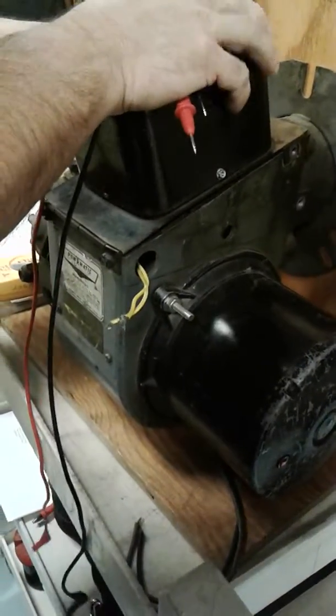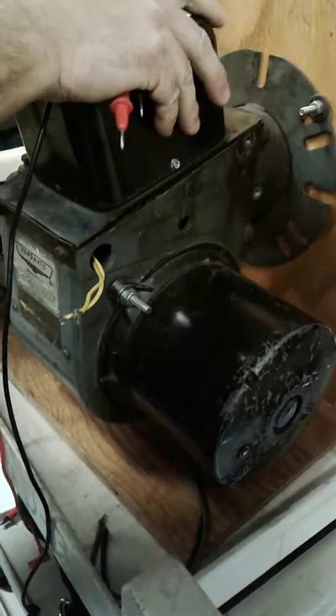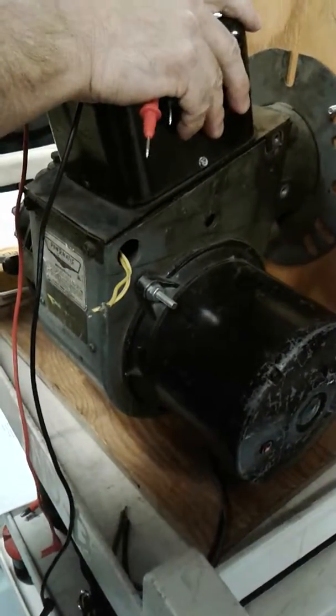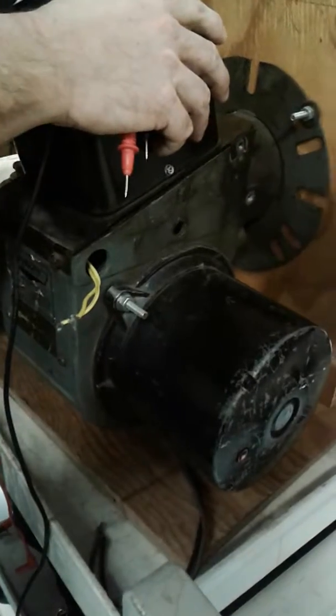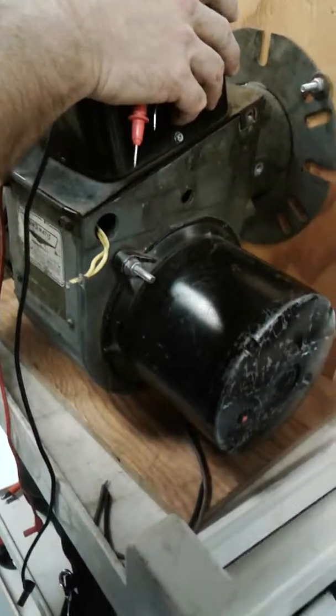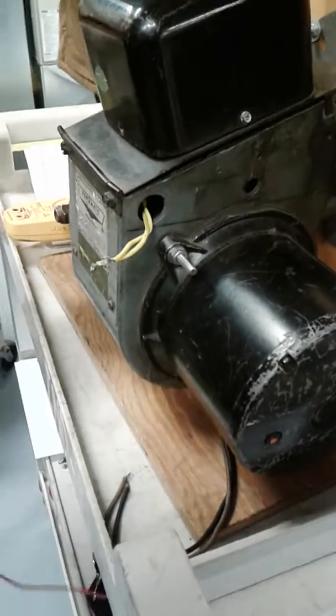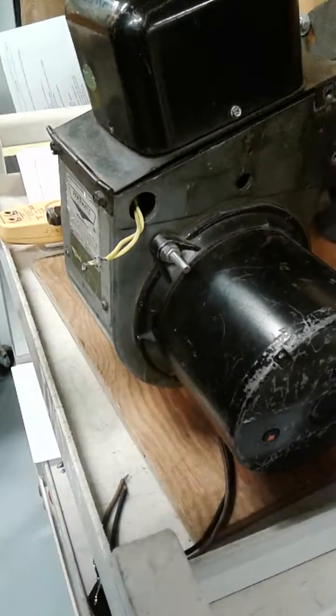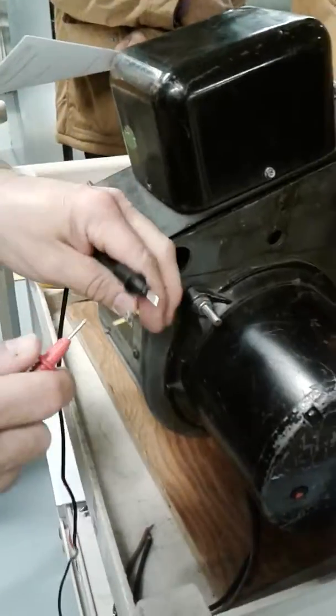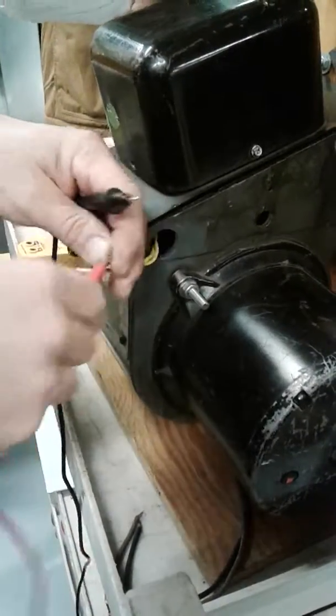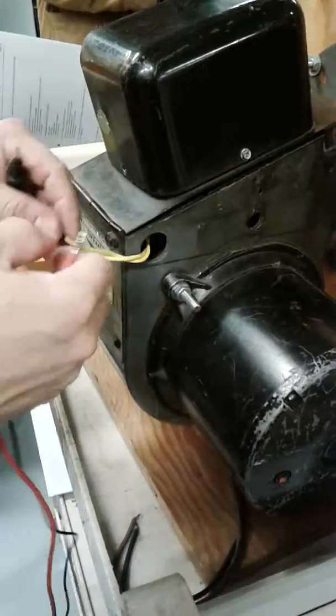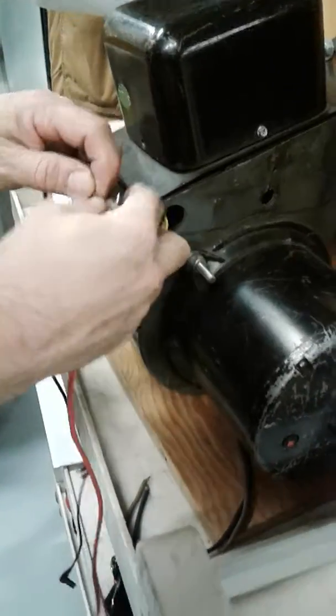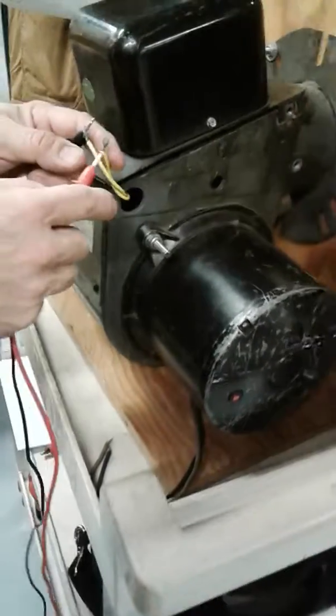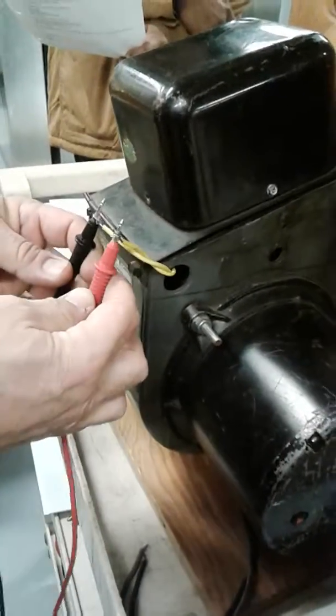We still are reading some type of light. It's not in total darkness. The reason why I say it's not in total darkness is because we're getting some light through the gun itself. Okay? So, somebody do me a favor. Stand in front of there, put your hand there, paper in front of there. Now we're in total darkness. Okay? Now, once you have it in total darkness, then you're going to be reading resistance along the CAD cell by checking the yellow wires. Okay? And then you're going to get some type of a reading, just like this.